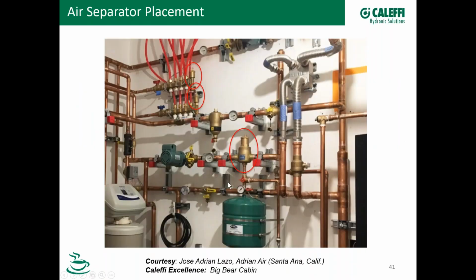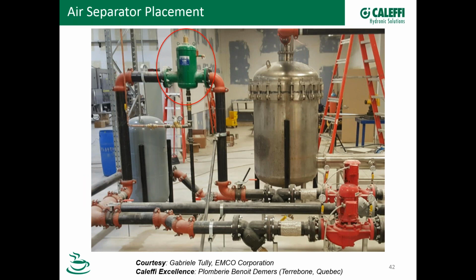Here's another picture I like. Here is a Discal, again, with, now here's the expansion tank and a valve hooked right to the bottom. So here's the filling location. Again, another magnetic dirt separator and a good picture of some air vents up on a manifold assembly. I like this commercial example here from EMCO up in Quebec. Here's a flanged version, and again, look, the bottom connection here is hooked to a fill valve. Now this is a 3/4 inch. It's a slightly larger commercial size fill valve with the backflow preventer here as well. This job isn't finished, but nice shot of a flanged Discal.